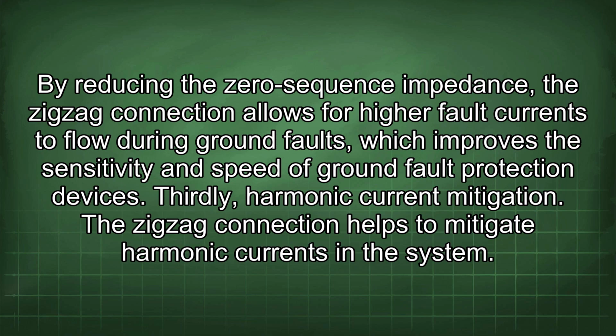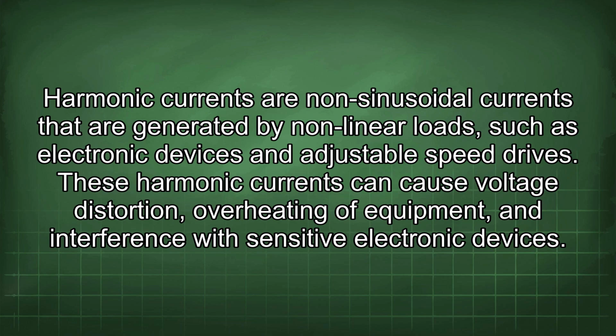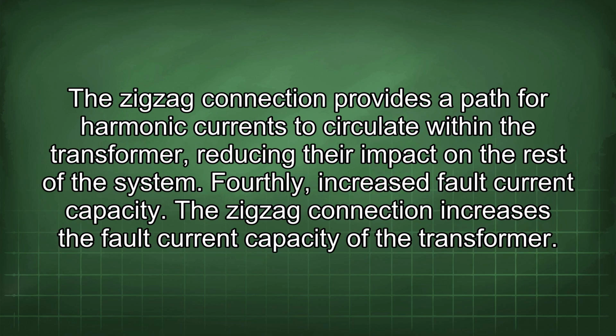Thirdly, harmonic current mitigation. The zigzag connection helps to mitigate harmonic currents in the system. Harmonic currents are non-sinusoidal currents that are generated by nonlinear loads such as electronic devices and adjustable speed drives. These harmonic currents can cause voltage distortion, overheating of equipment, and interference with sensitive electronic devices. The zigzag connection provides a path for harmonic currents to circulate within the transformer, reducing their impact on the rest of the system.